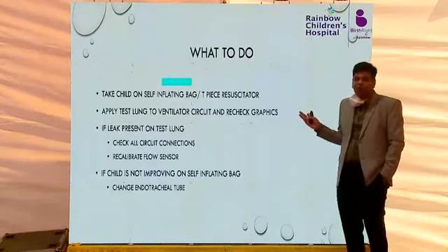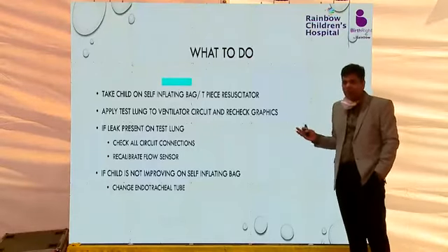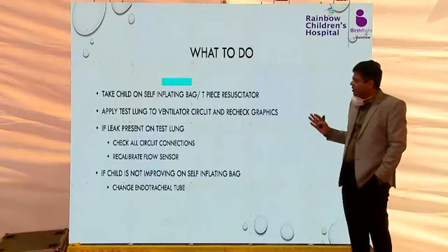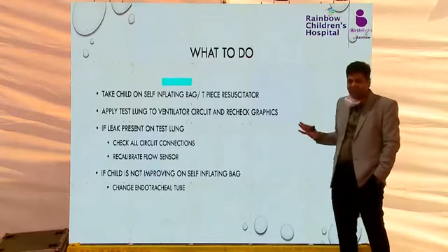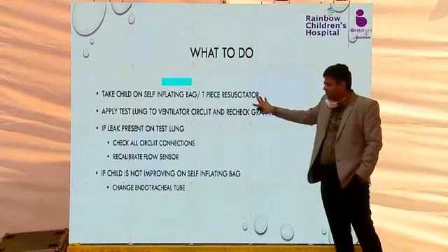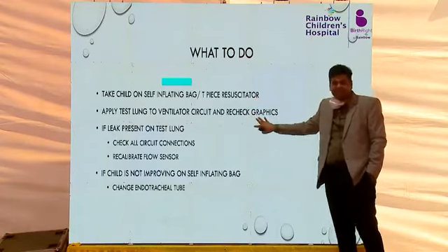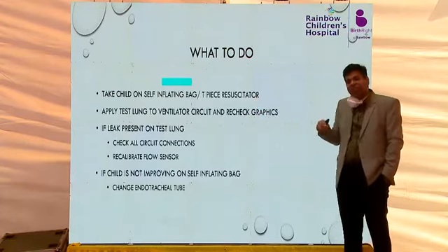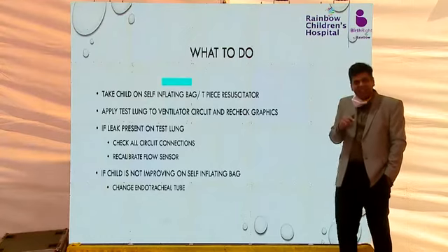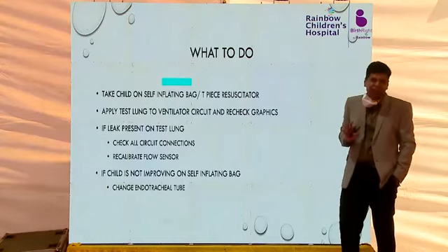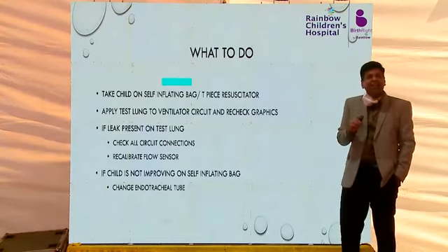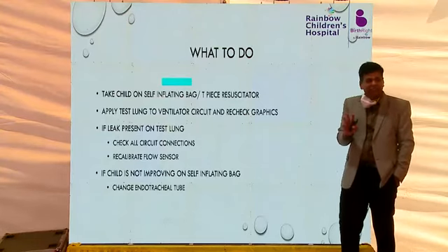So now what to do in this scenario is you can take the child off the ventilator, use a self-inflating bag or the T-piece resuscitator, and tie a test lung to the ventilator circuit. Then you see whether, with the application of the test lung, the leak is still that much or not.